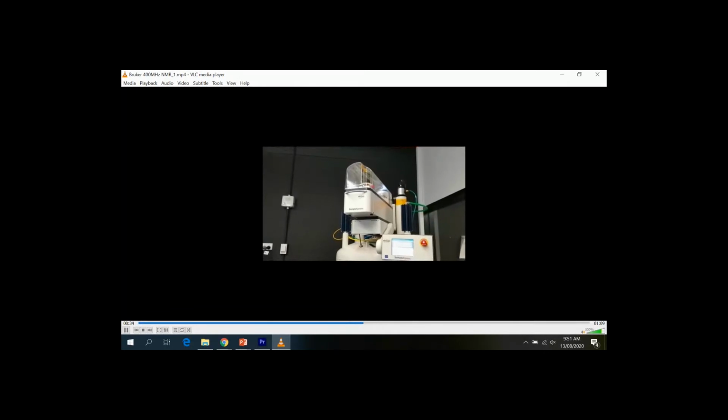So basically you push start, you'll see there's a green light at the top there. You then jump over to the computer and say, yes, I want to start a program. You then come back and have a look at the sample express at the top. You'll see that it's slowly starting to spin and move around. So that's why I was meaning like a conveyor belt. And you'll see that there is a red light flashing. When it turns green, that's basically saying to us, yes, your sample's ready to load and be detected. So there's that green light. And then you head back to the computer and you can start to see your spectra starting to form.